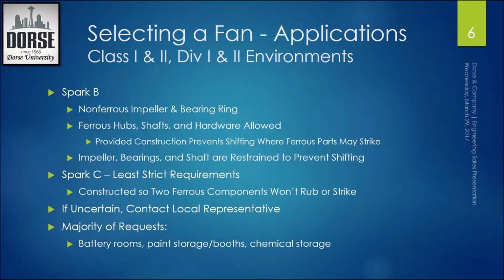And then Spark C, simply the least strict, just constructed so that no two ferrous components will rub or strike together. And if you're ever uncertain, just contact us or your local Greenheck representative and we'll go into more detail and help you select a fan to meet your needs. Most requests we receive are for battery rooms, paint storage booths, and chemical storage applications.